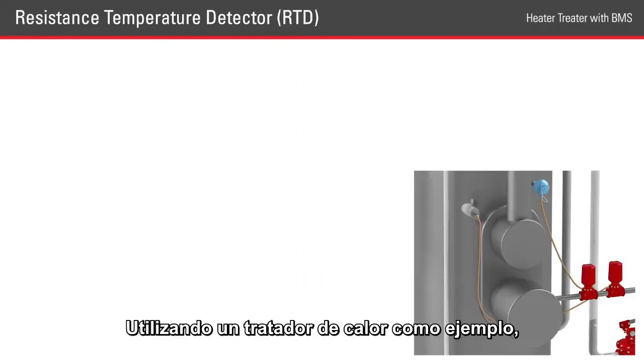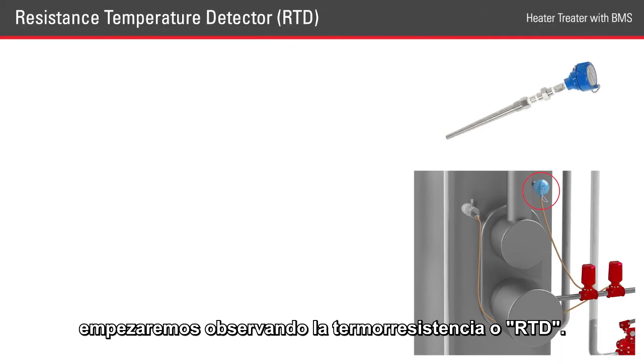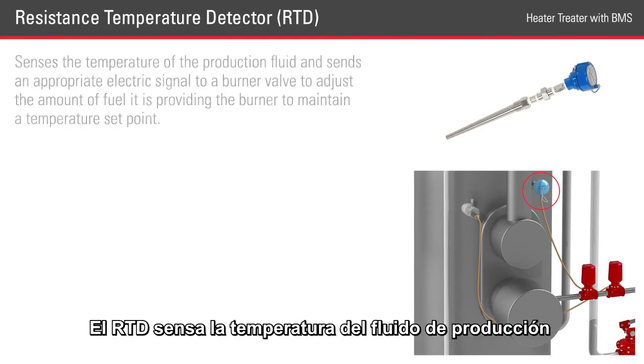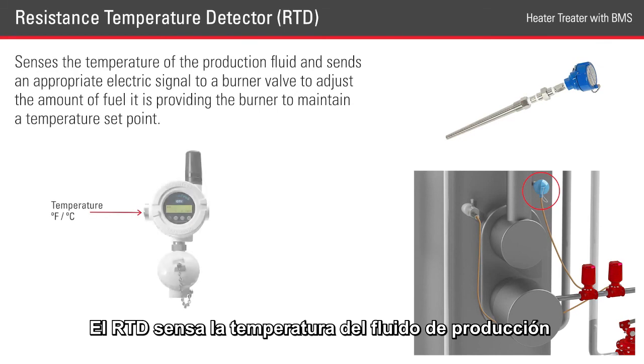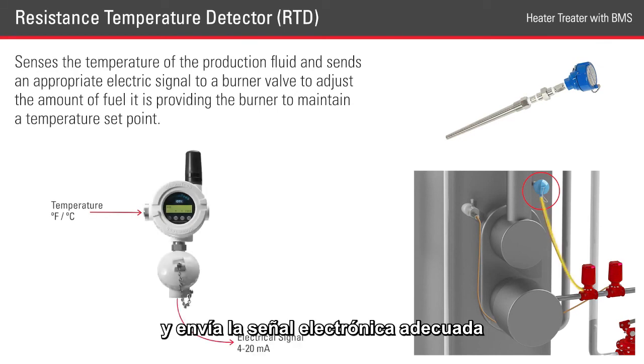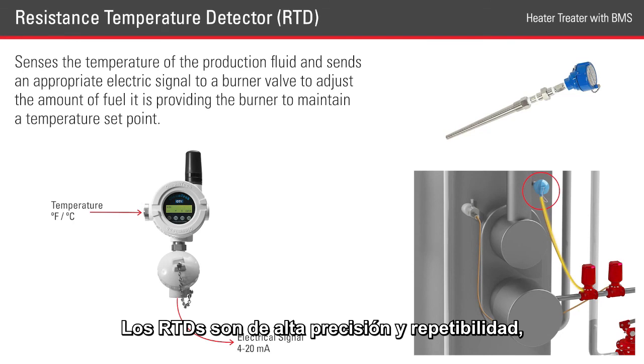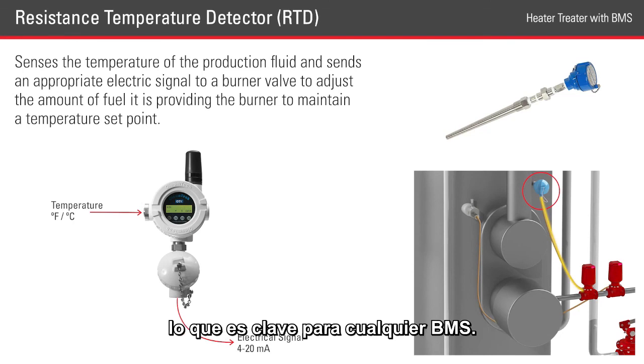Using a heater treater as an example, we'll start by looking at the resistance temperature detector, or RTD. An RTD senses the temperature of the production fluid and sends the appropriate electronic signal to the burner valve to adjust the amount of fuel it's providing to the burner to maintain a temperature set point. RTDs have high accuracy and repeatability, which is key to any BMS.